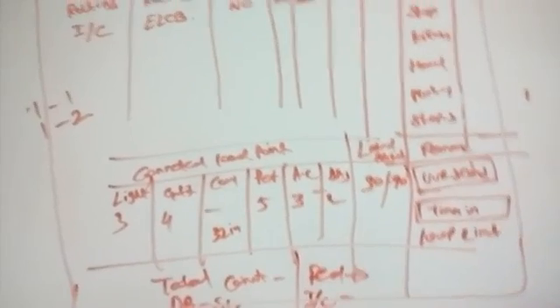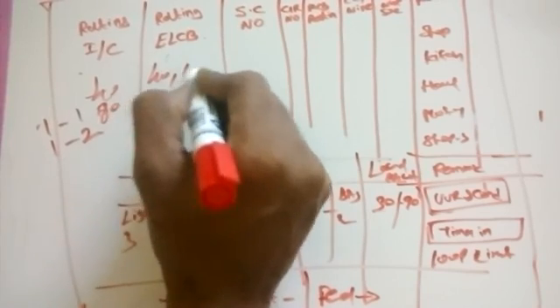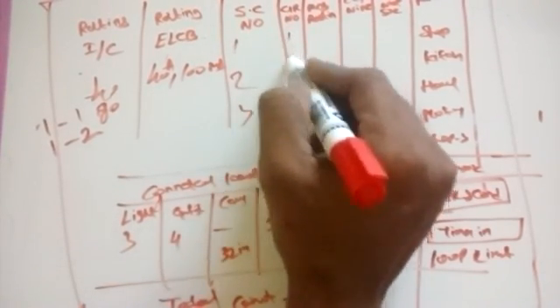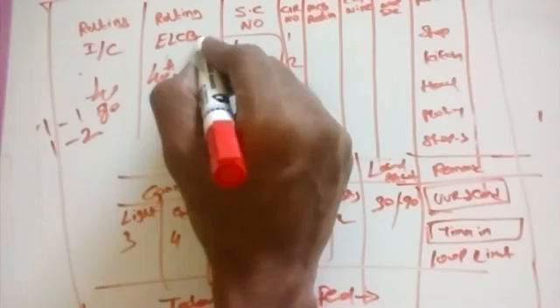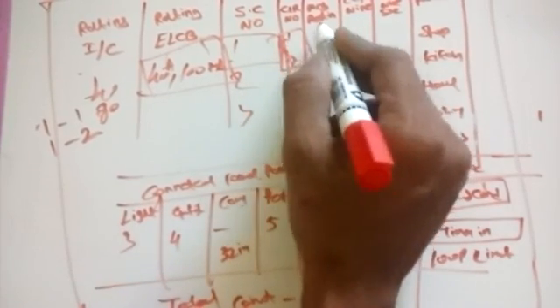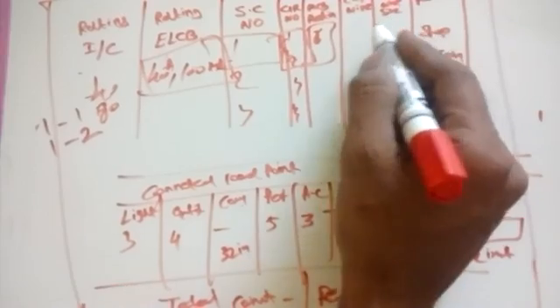This is the simple method. For example, the incoming rating might be an isolator of 40 ampere or 80 ampere. The ELCB rating could be 40 ampere at 100 milliampere. Sections are numbered 1, 2, 3 and circuits are numbered 1, 2, 3, 4, 5. In one section with a 3-phase supply, you may place 6 or 7 MCCBs. The CCT wire size and ECC wire size are also mentioned here.